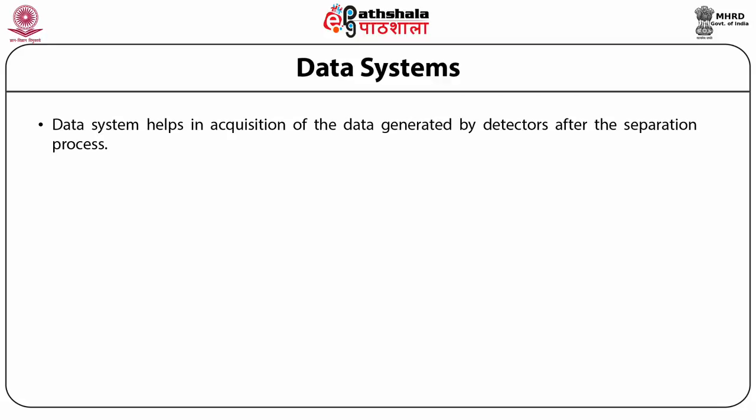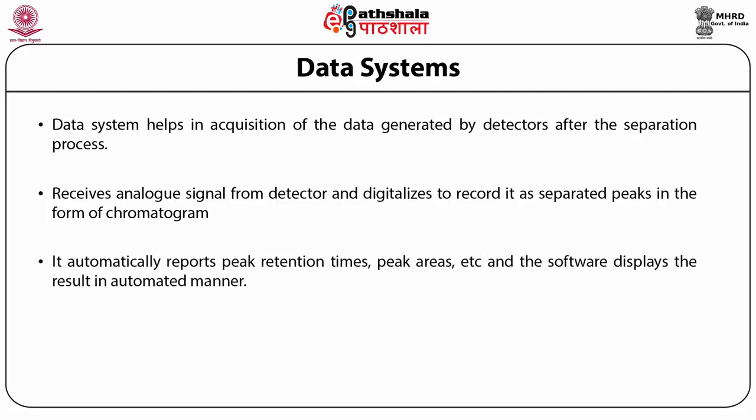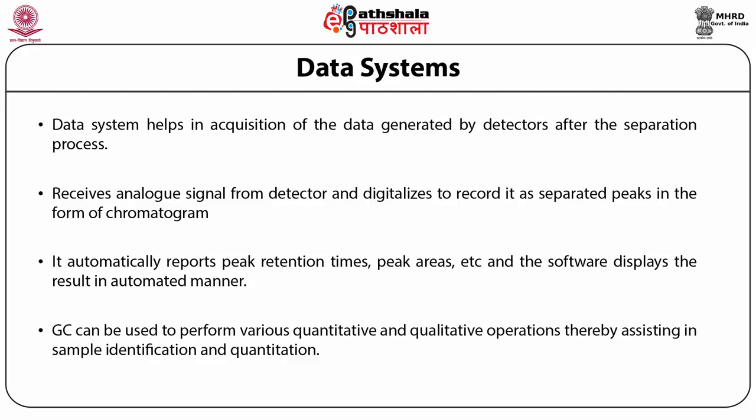The data system helps in acquisition of data generated by detectors after the separation process. It receives analog signals from the detector and digitalizes them to record separated peaks as a chromatogram. It automatically reports peak retention time, peak areas, etc., and the software displays results in an automated manner. Thus, gas chromatography can be used to perform various quantitative and qualitative operations, assisting in sample identification and quantitation.